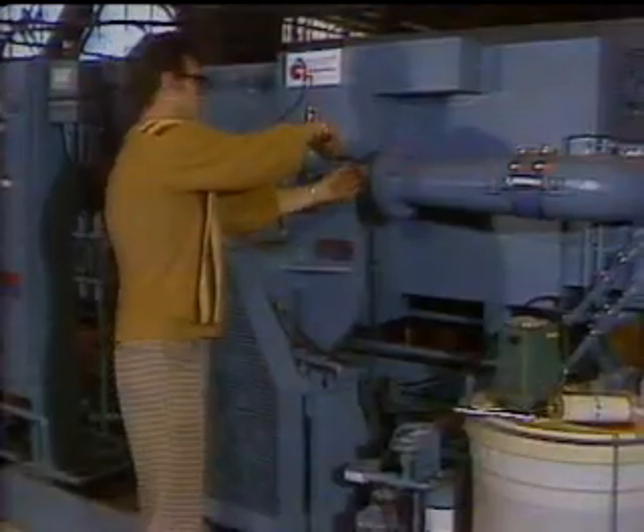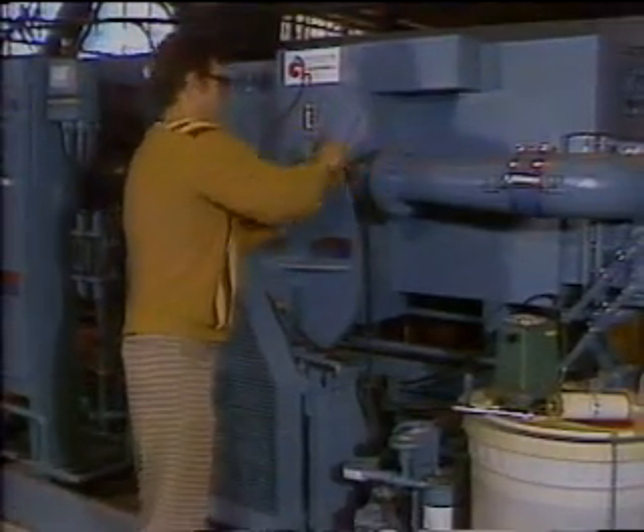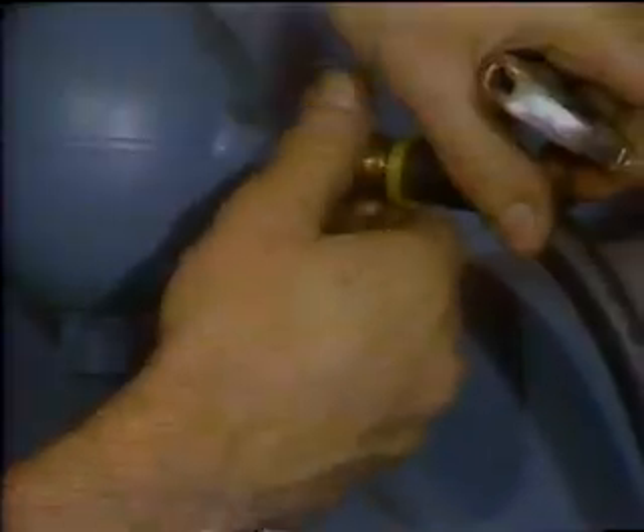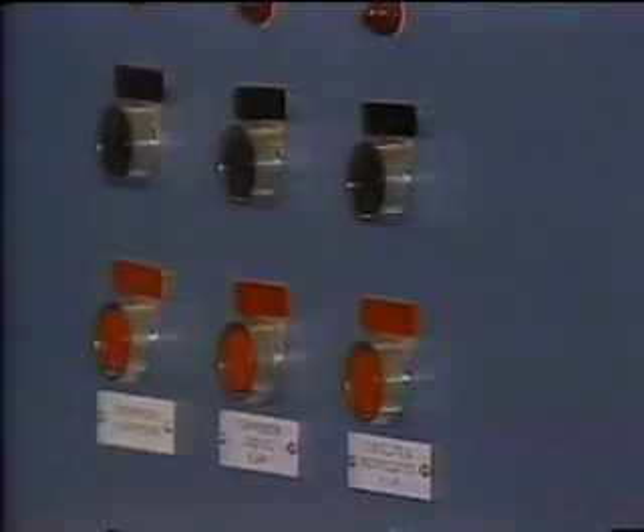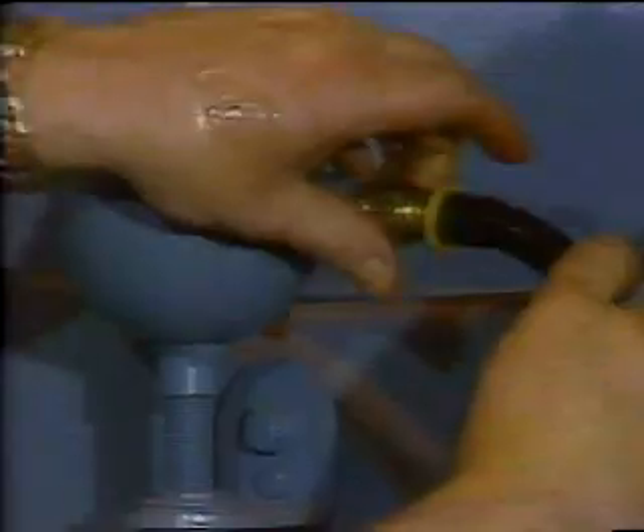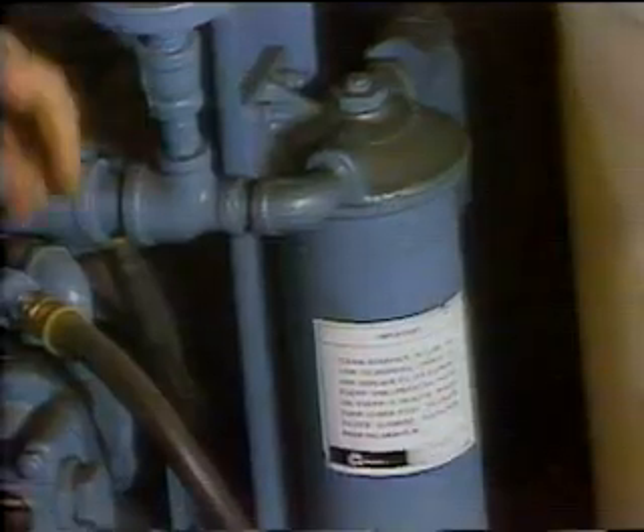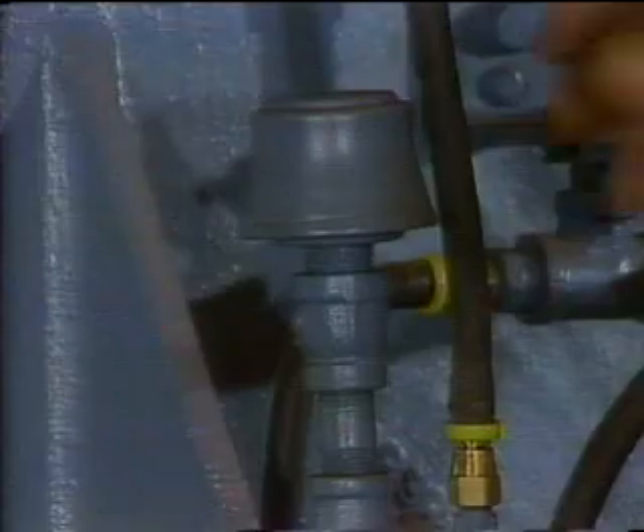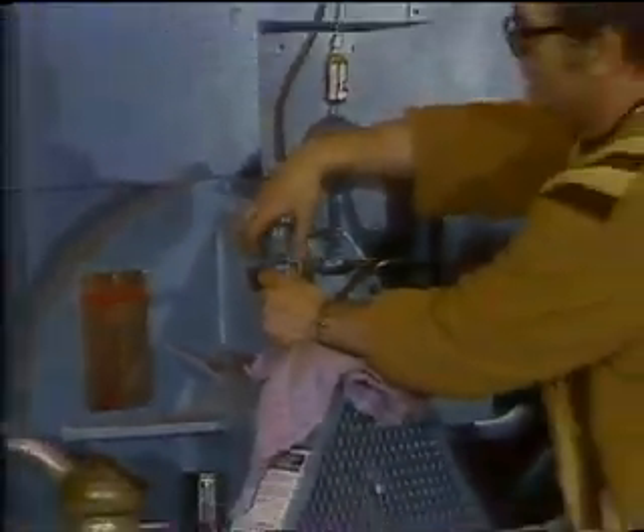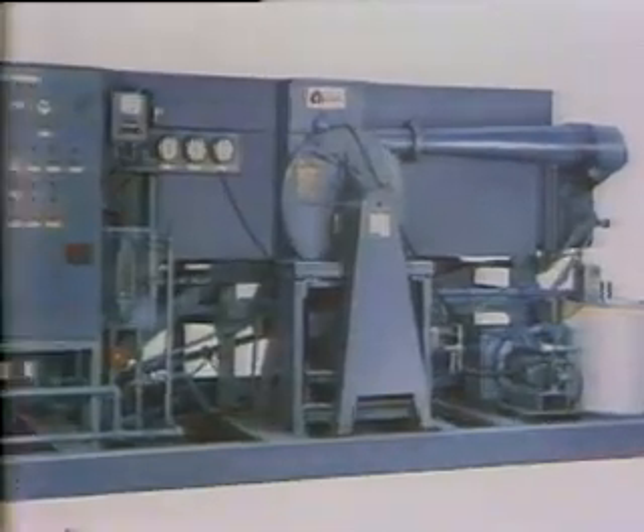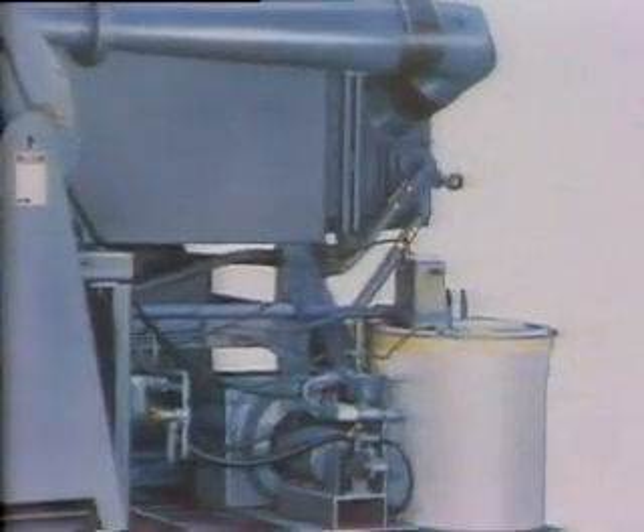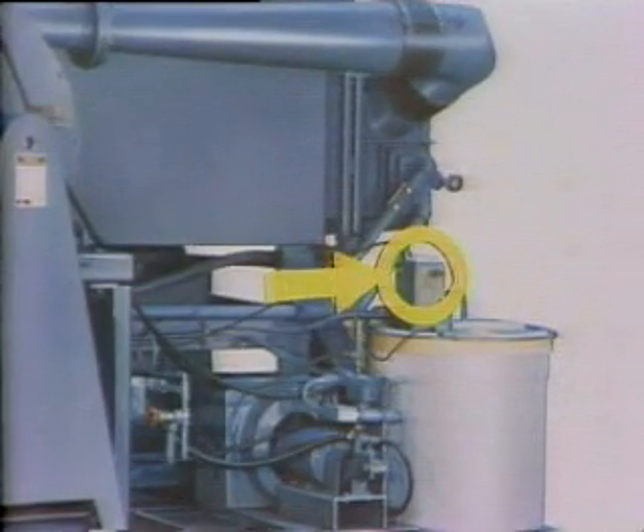At 2,000 hours, you'll need to change the oil filter and oil in the centrifugal compressor oil pump. First, remove the discharge hose at the head tank. Turn the pump on so that the old oil will be pumped out of the system. Then turn the pump off and replace the hose, change the filter, and refill the system like we did earlier. Also at 2,000 hours, you'll need to change the oil in the chemical treatment pump. Check your maintenance manual for this procedure.